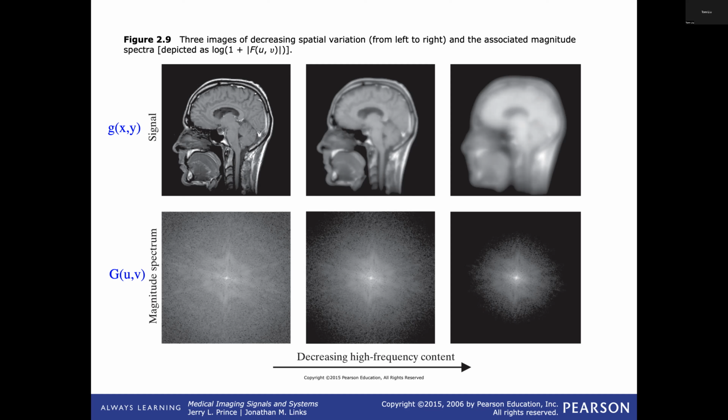Sometimes the amplitude is the same, but the raw data gets phase shifted, and that happens with flow, for example, or movement, like if the patient's breathing. And then here's some other things, like say I'm taking a picture of a patient and their chest and they're breathing, okay? When I look at a pixel that's right near their chest wall, as I'm acquiring this raw data, that pixel will blink on when they breathe such that their chest wall intersects that pixel value. And then when they exhale and go down, that pixel essentially blinks off.